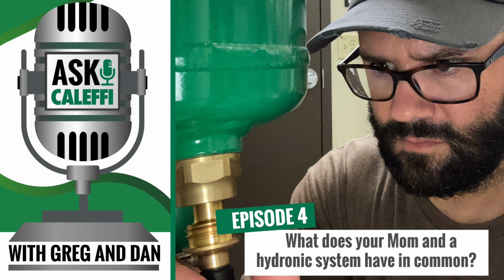Certainly can. And then those larger commercial units have a 3/4 piece of standpipe off the top that's threaded, and that big 502 air vent. Yep, the Max-Cal, the 501, 502 Max-Cal. I've seen people put that on there as a secondary. I don't think you can ever have enough air vents in a system if they're placed properly. Yep, I agree. You're going to have an air separator on the supply side, a dirt separator on the return side, and air vents within the system. Why not throw an air vent on top of that dirt separator and get a little bit of additional air removal?